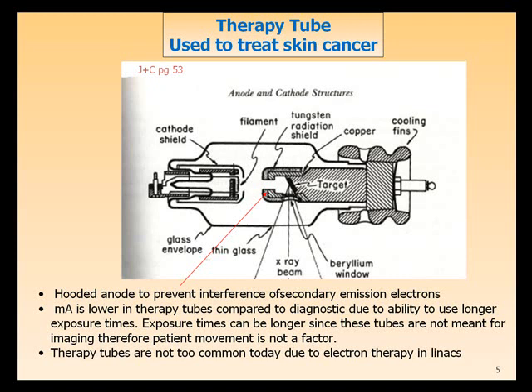There's a different kind of X-ray tube called a therapy X-ray tube — just what the name implies. It's not used for imaging, it's used for therapy, for treating something. The things we typically treat with this kind of tube are superficial diseases — mainly skin carcinomas. There are two types: basal cell and squamous cell, and then melanoma, the worst one.